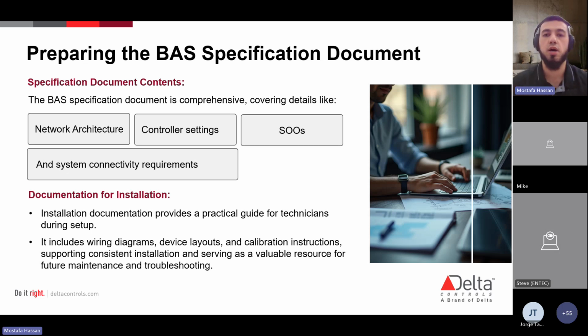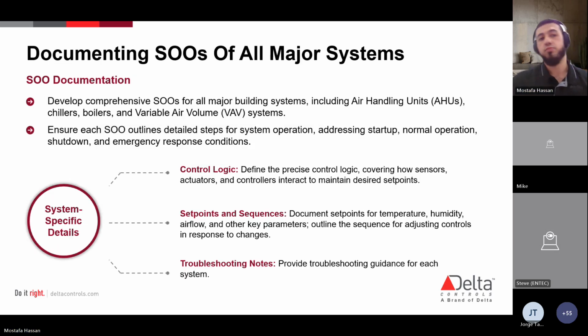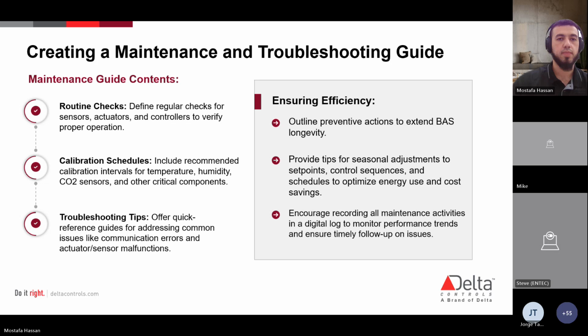Then you have details on installation, right? The specifier is going to make sure that there's a document showing how to actually install each item, each product, each controller, and that for future maintenance, the building operator knows what to do and how to troubleshoot future issues. It's kind of repetitive here, so you're documenting, again, your sequence of operation for all major systems, and then you're creating maintenance and troubleshooting documentation. You're doing routine checks and specifying that as well. You're going to define and specify regular checks for sensors, actuators, and controllers.